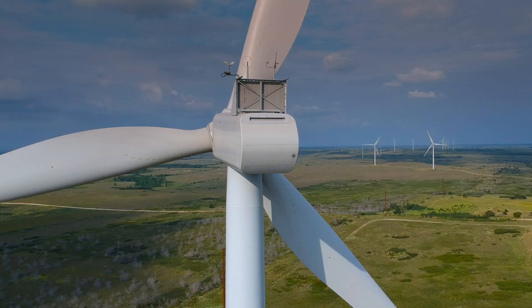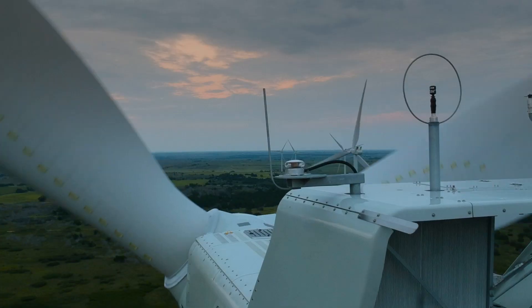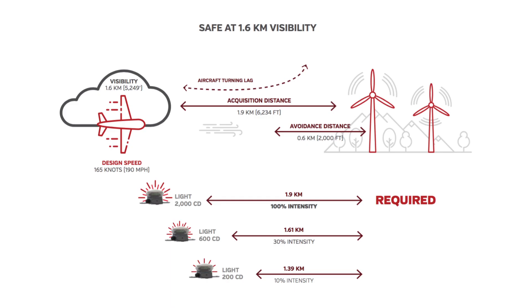One of those impacts that can be managed is the brightness of obstruction lights at night. The Federal Aviation Administration requires obstruction lights to produce 2,000 candela of intensity during the worst visibility conditions. Visual flight rules dictate that a pilot is allowed to fly with a minimum of one statute mile of visibility.